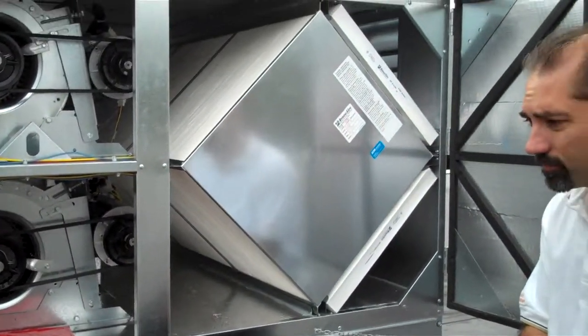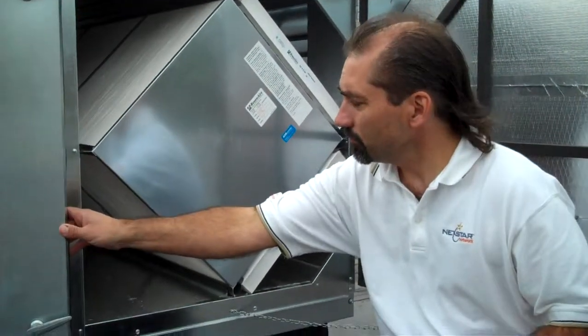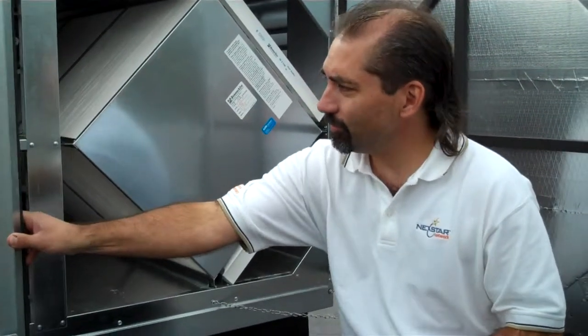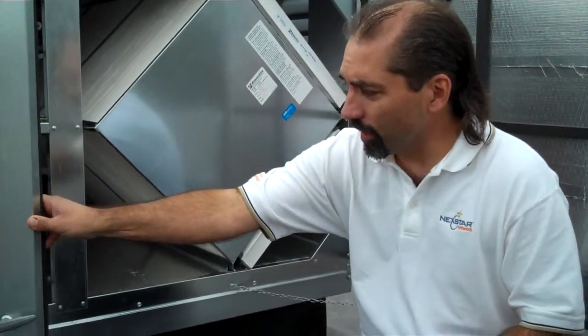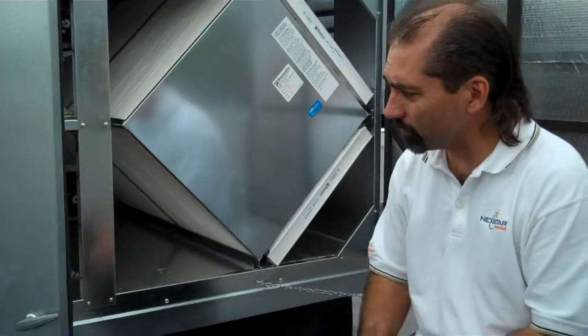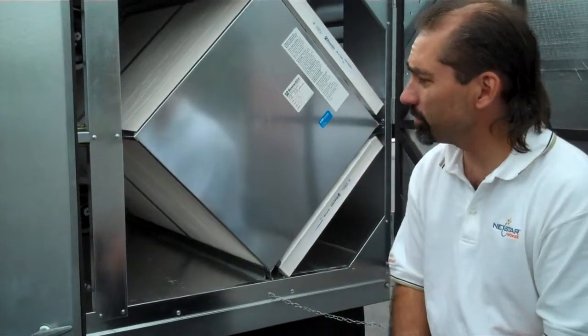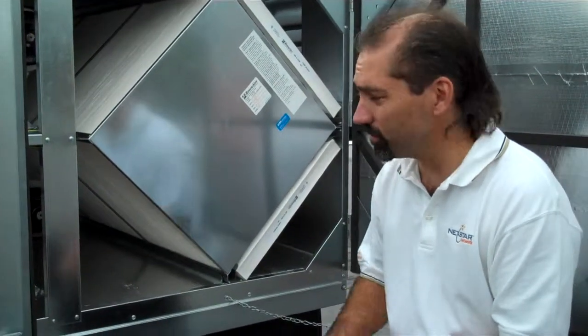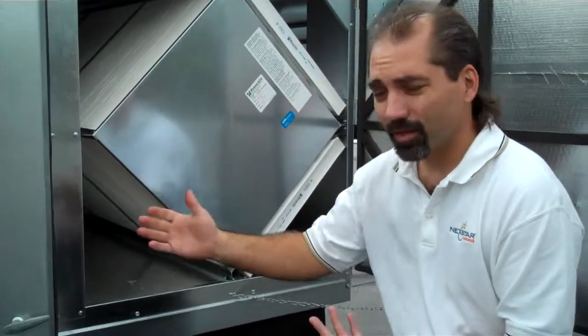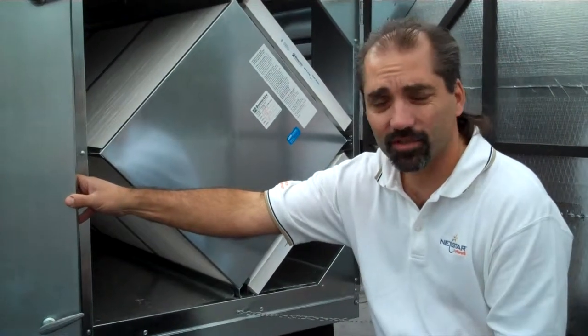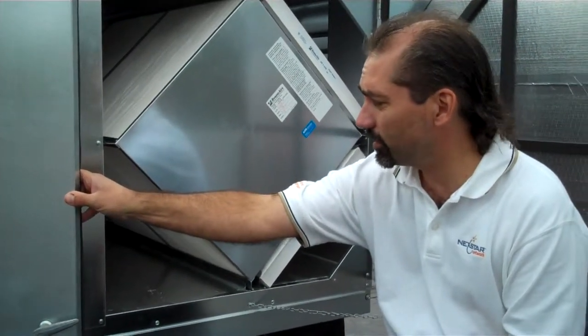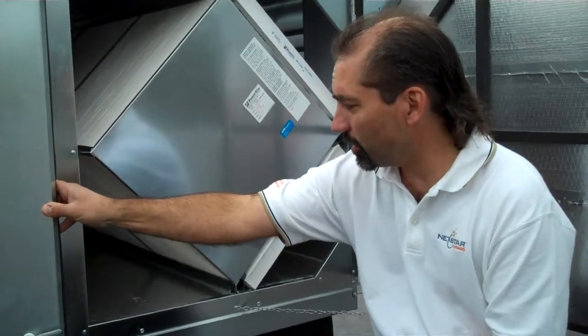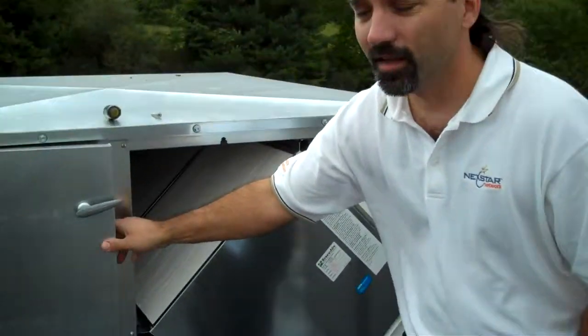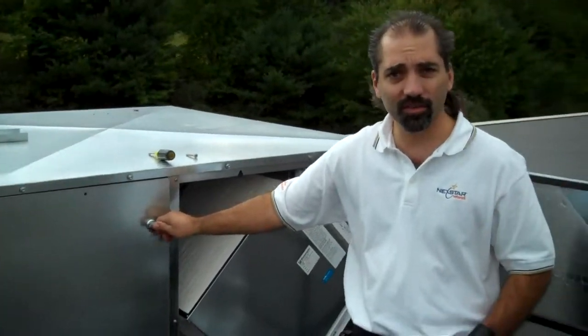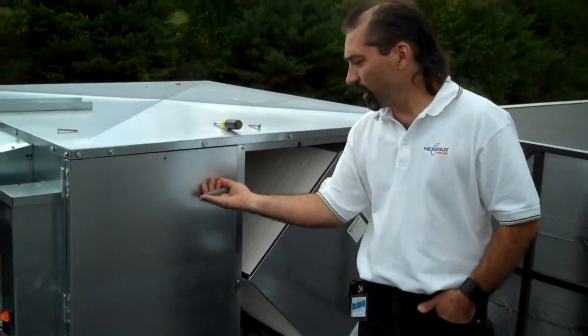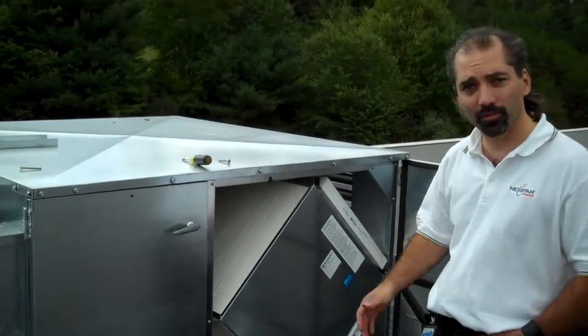That's correct. And any precautions that people should take, other than the wind blowing the door shut on you? Other than the wind blowing the door shut, just preventative maintenance on the system. Obviously belts, grease and bearings, motors, filter changes, core changes, operational checks, making sure that the voltages, amperages, and stuff like that are all within the specs of the units. But pretty much we're going to set these up on a time clock, so that when school is in the occupied mode, the system will run and do the energy recovery, and then when the system closes down for the end of the day, we'll turn them off.